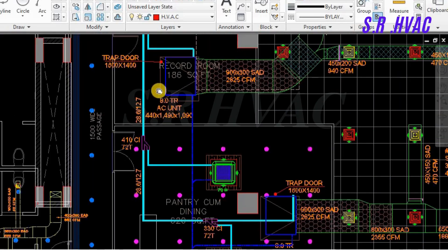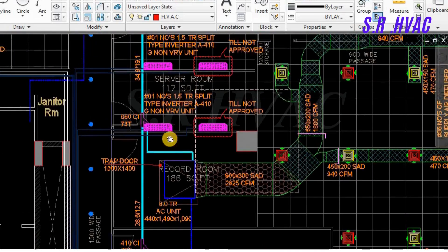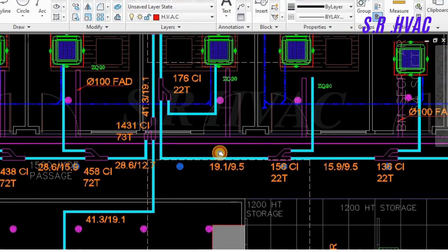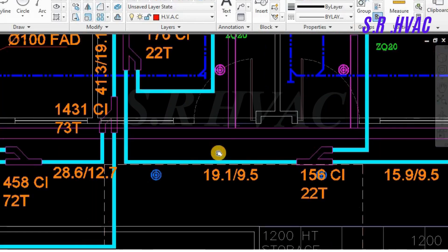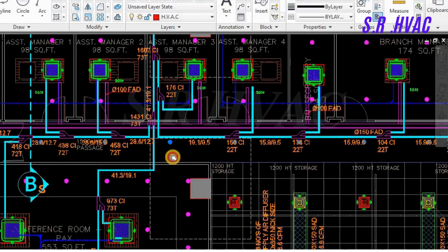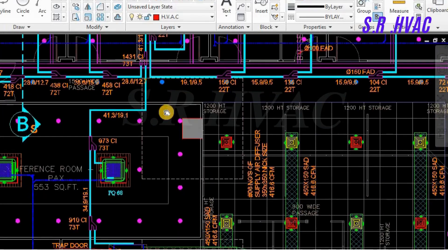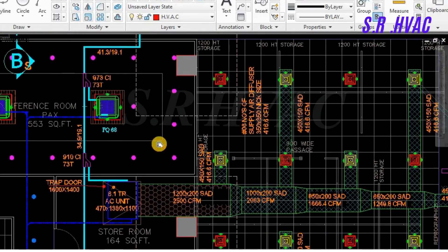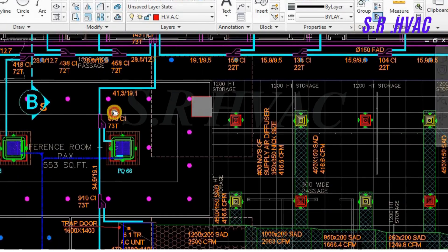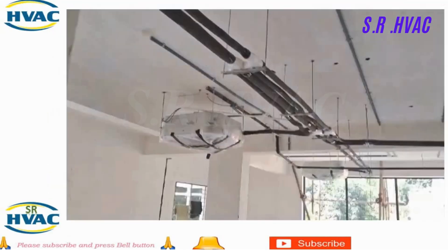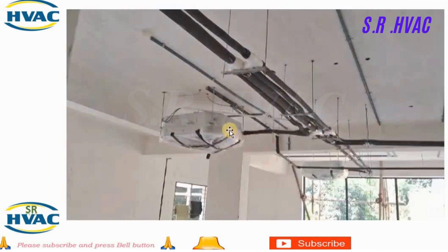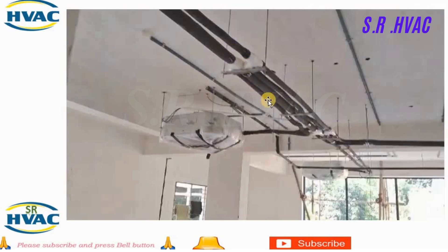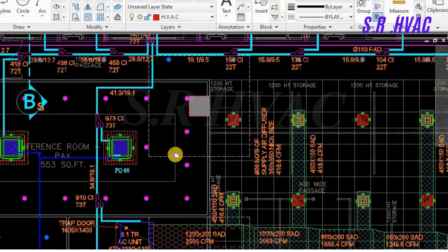Friend, before doing the pipe we have to inspect all the areas whether it is free or any fire line or something is coming, so that our execution goes smoothly. We have to coordinate with all the other contractor also. You can see the copper piping, I will show you one picture of copper piping also. See, this is the copper piping we have done, this is our unit. We have done it, you can see we have hanged with the help of threaded rod 8mm and C channel, and we have covered this Y joint also. You can see, this is how we hang our copper pipes and machines.